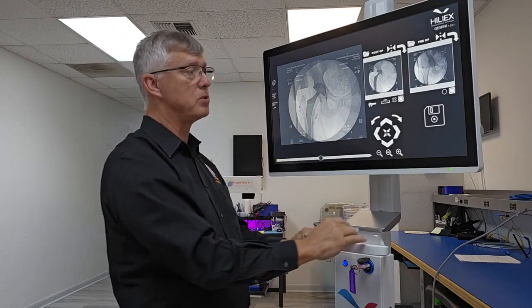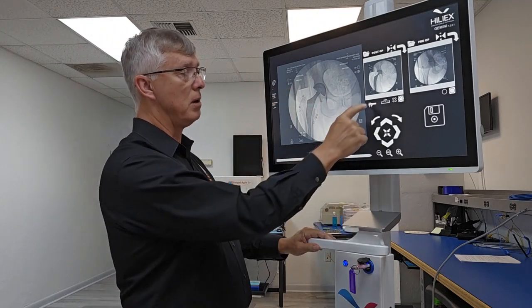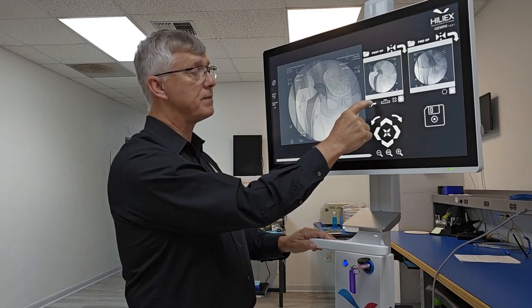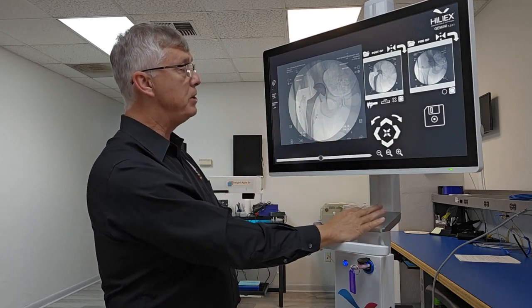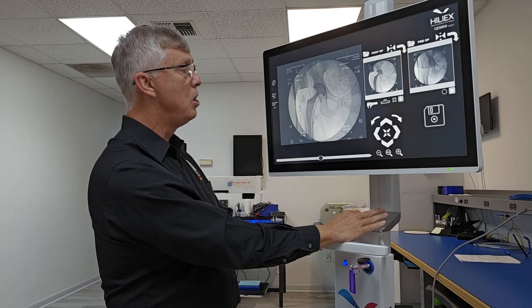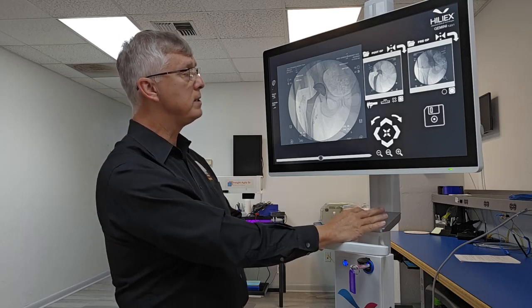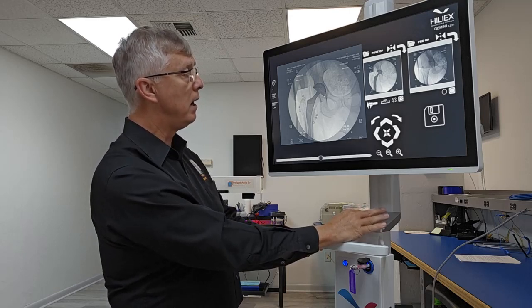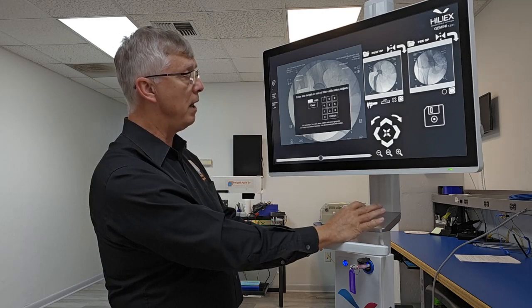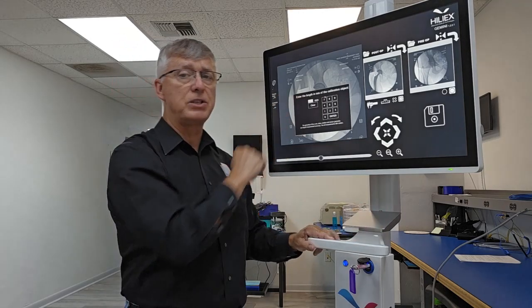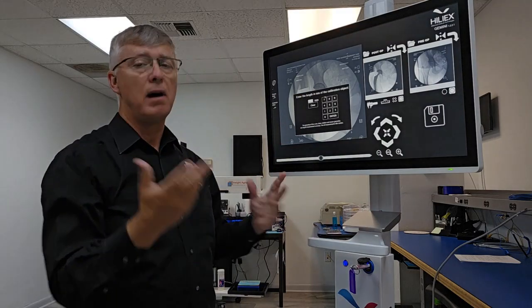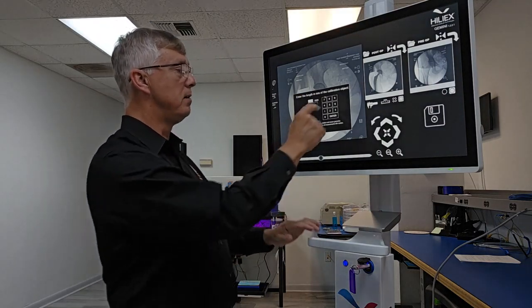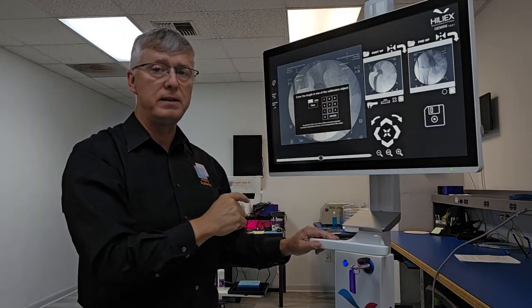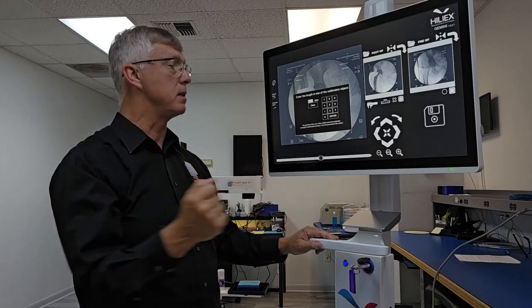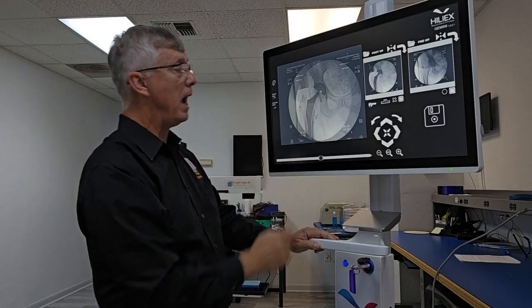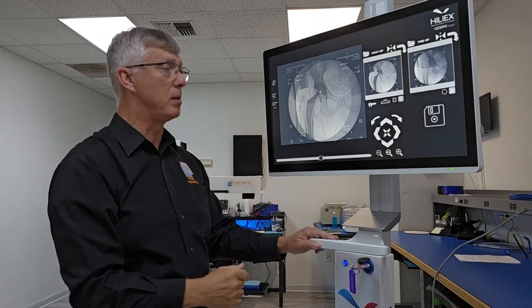If you want to make measurements, first you have to do a calibration. So you have a little caliper, and that's for calibration. We touch that. And here I do recommend using the mouse. You just click on one side of the cup and click on the other side of that cup, and it's going to ask you for how big that cup is. I'm going to choose 52 millimeters. So you put in the cup size, the diameter, which is on the box label, and hit enter. And now it shows me, that's my calibration.